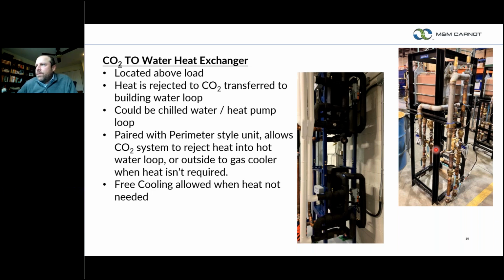The row-based cooling units are about 40 kW a piece, but we are looking to develop another row-based cooling unit that will do about 100 kW worth of cooling in a fairly small footprint in the data center. With CO2 able to hold more heat than the synthetic refrigerants, we need less heat exchanger area. So our heat exchangers can be smaller, whether it's your evaporator coil or your condenser, which makes our units a perfect application for a retrofit system. If you had something that's using synthetic refrigerants that you want to eliminate, I haven't seen a case where our units at the same capacity are anything but smaller in size. The footprint for a synthetic refrigerant system is bigger, ours is smaller. So it makes it easy to upgrade facilities with natural refrigerants that were historically using synthetic refrigerants.